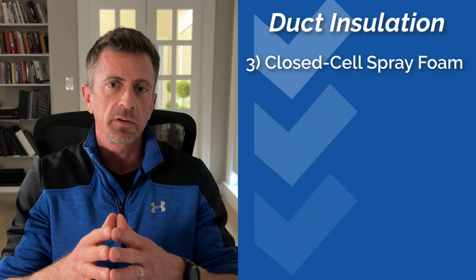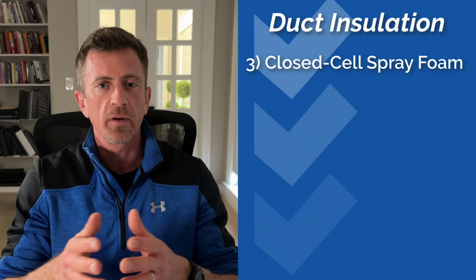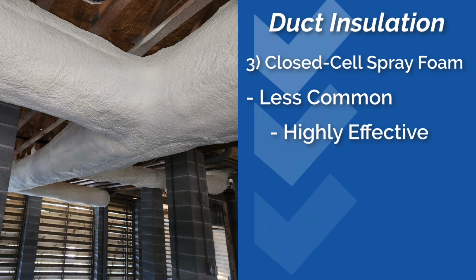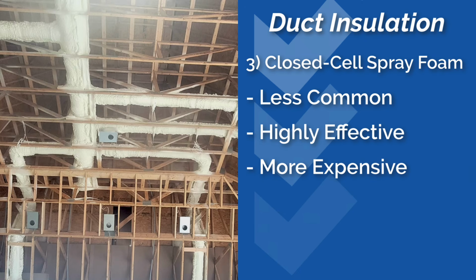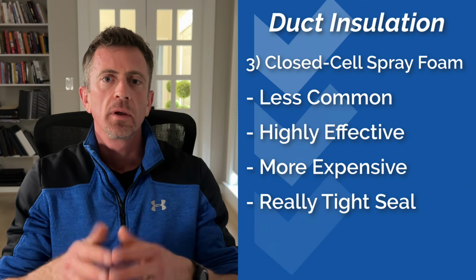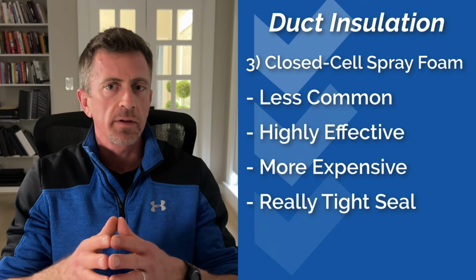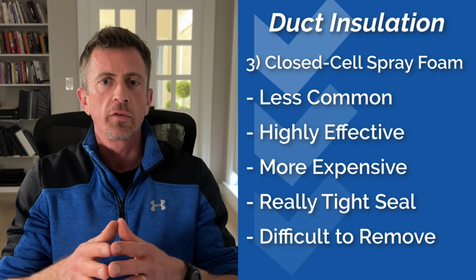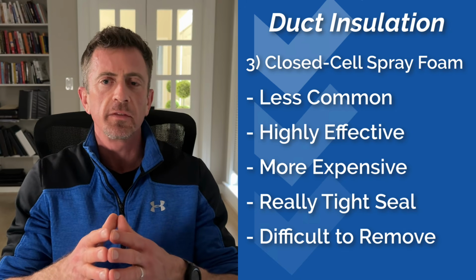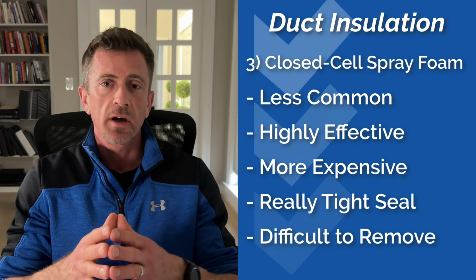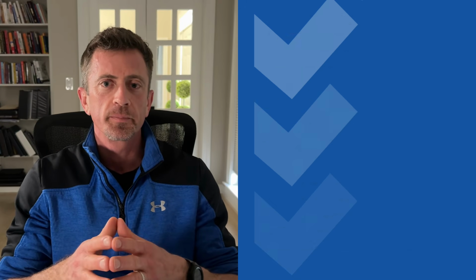The last insulation type is closed cell spray foam. This is a less common but a highly effective way to seal and insulate ductwork. It's more expensive than other methods for sure, but it creates a really tight seal and provides excellent insulation that generally won't degrade over time. The main drawback, other than the cost, is that it's really difficult to remove from the ductwork if there's ever an issue that needs to be fixed later on. Once it's on, it's really on for good.